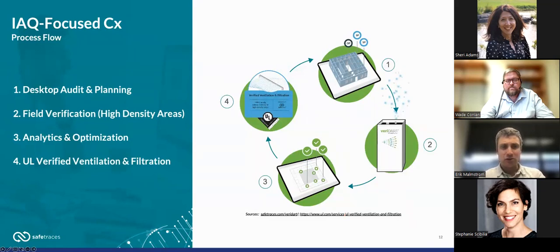Based on that data, we look to see whether the tested spaces are achieving the performance bar set by the UL verification mark. If not, we identify deficient areas and help figure out what's going on and how they can be brought up to the performance bar. Also importantly, in some spaces they may be overventilating, giving an opportunity to adjust set points and reduce cost and energy penalty. So optimization can go both ways: addressing deficient areas, but also dialing back set points elsewhere. Finally, the UL verification mark is the last step, communicating this to building occupants through an annual verification program.